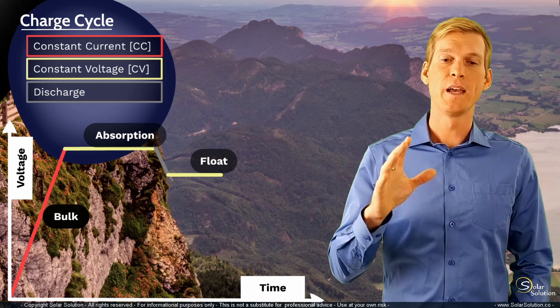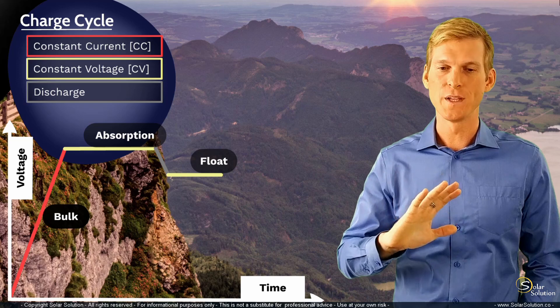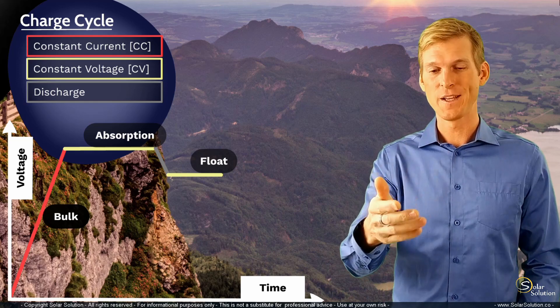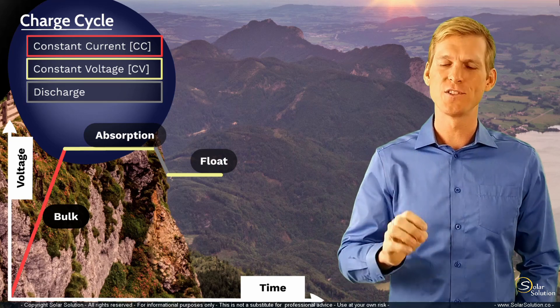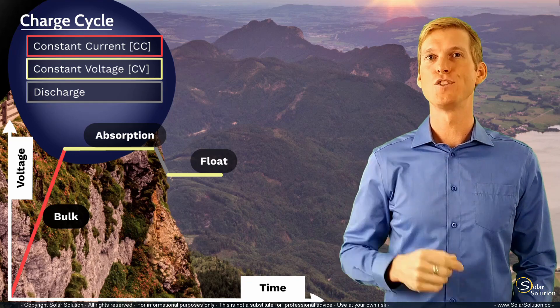And this is to compensate for the self-discharge of the battery. Because each and every battery has a certain self-discharge rate, so if you wouldn't do anything, if you wouldn't be charging or discharging the battery by your action, the battery would still lose energy over time. So therefore, in the float stage, you're still adding a little bit of energy to keep the battery at 100% state of charge.